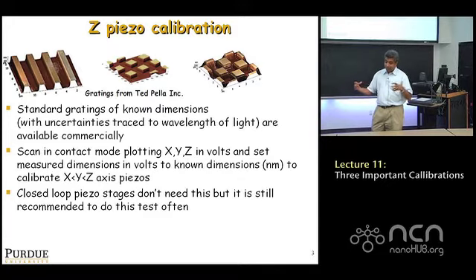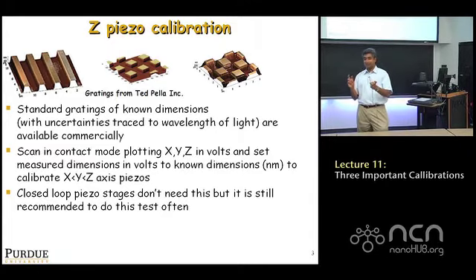How is it doing it? Or how do you make sure the conversion is correct? Well, you got the image in volts versus volts versus volts, and you know the dimensions of this grating in the XY direction and in the height direction, right? So you say, okay, in my image, I'm measuring the width of this particular object as 10 millivolts, and it's supposed to be 100 nanometers. Therefore, along the X direction, 10 millivolts equals 100 nanometers, right? You do the same along the Y direction. You do the same for the height, okay? So this is how you convert it, and this number is usually buried somewhere inside the AFM software, this conversion.